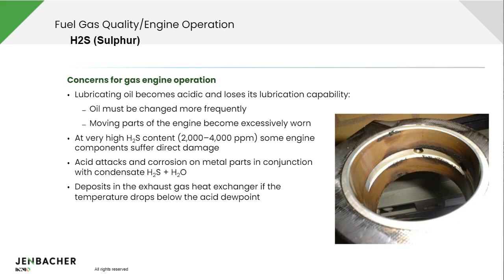If we look at the exhaust heat exchanger, which I just mentioned, this is a picture which really shows what sulfur can do. It forms all these deposits there, corrodes the material. And one way to partially avoid the problem is to keep the exhaust temperatures higher, so be above 356 degrees Fahrenheit at the exit of the exhaust heat exchanger, so you don't extract that much heat out of it, and that prevents condensate, which is one of the main issues, as that forms sulfuric acid with H2S.